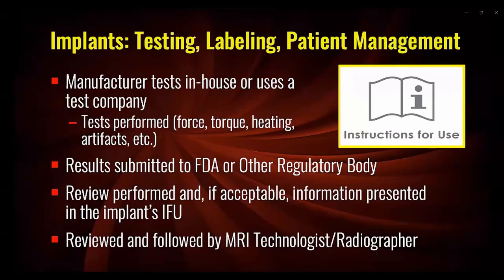The technologist carefully follows the labeling, which involves making sure that the relevant conditions are met to ensure patient safety. Be aware that in the vast majority of cases, the MRI testing and labeling typically only applies to 1.5 and/or 3 Tesla scanners, because these are the primary MRI systems used for clinical imaging worldwide.